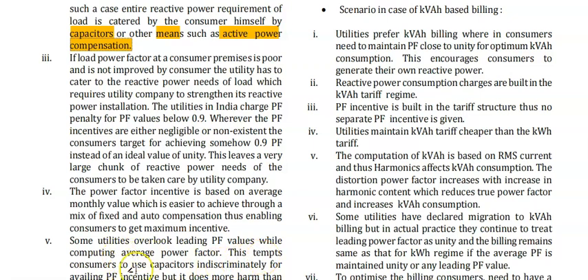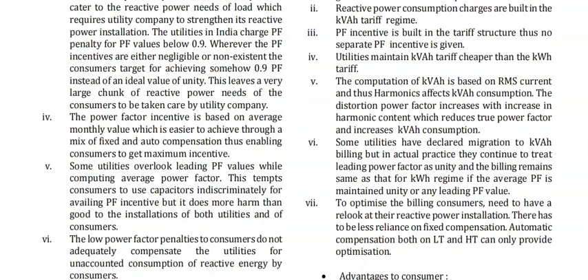This tempts the consumer to use capacitors indiscriminately for availing the power factor incentive, but it does more harm than good to the installation, both for utilities and consumers. The low power factor penalties to the consumer do not adequately compensate the utilities for the unaccounted consumption of reactive energy by the consumer.